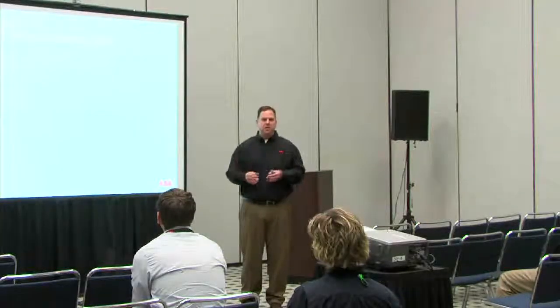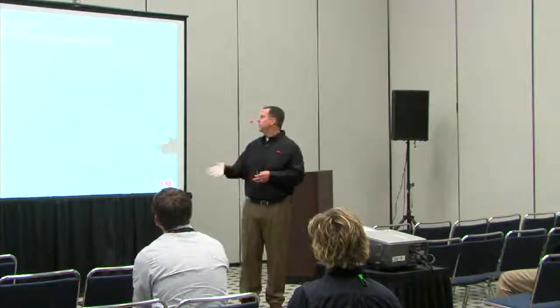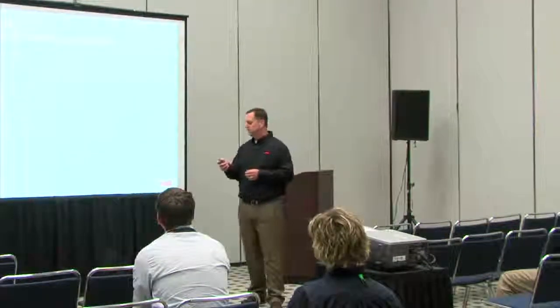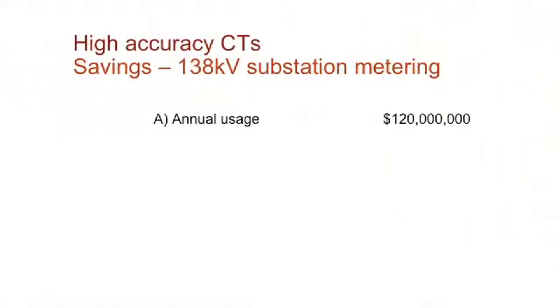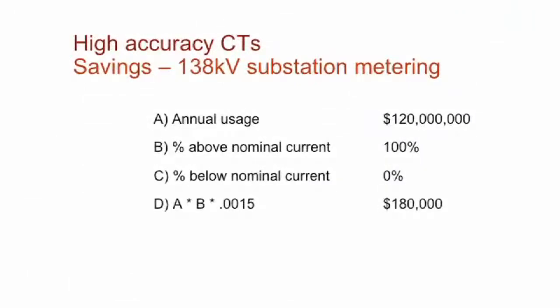So a municipal, a co-op, or even an investor-owned utility would buy power from a transmission or a generation company, and maybe they want to add second metering check just to make sure they're paying the right bill, as it would be a good example. Time above nominal current. Okay, you spend the money, tens of millions of dollars on a 138 kV substation. Generally, that's going to be above nominal current all the time. So percent below nominal then would be 100 minus 100, obviously would be 0. But if we do the math there, okay, we can see the savings would be very, very significant. Okay, up to $180,000 a year.